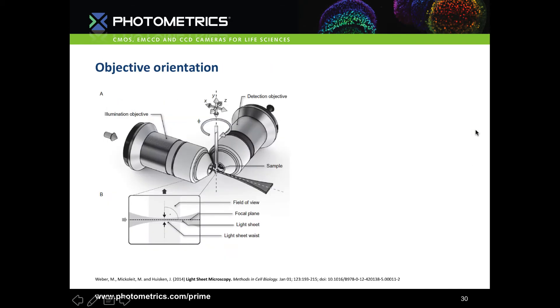The objectives are really the core of the lightsheet system. They are very close together, which is why lightsheet objectives mostly range from 2x to 40x but not usually larger. The working distance of the detection objective has to reach the lightsheet, and high magnification, high NA objectives — particularly oil immersion — have a working distance far too short for that. There are some 60x implementations, but people mostly work from 2x to 40x.